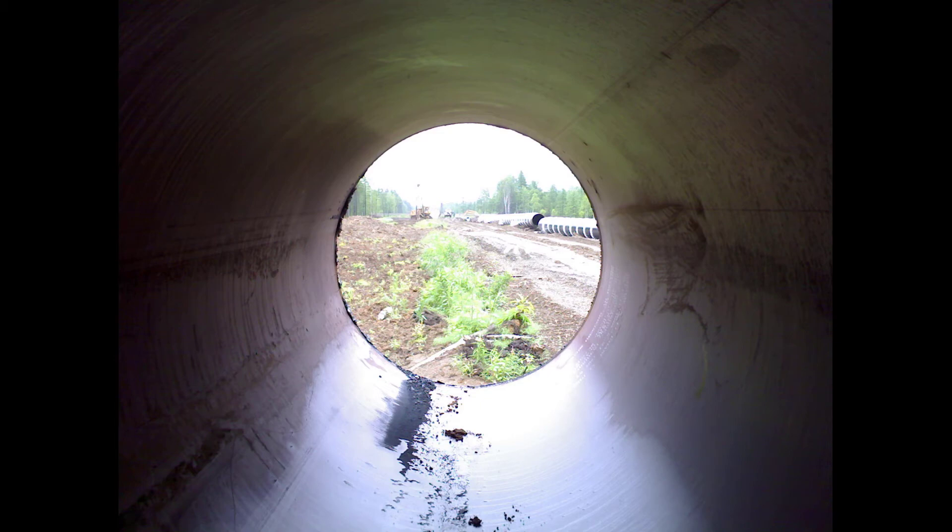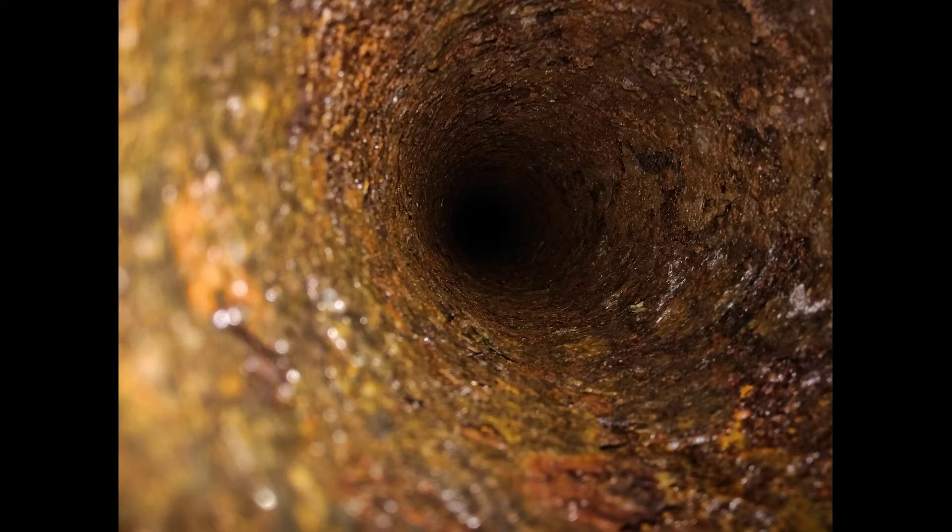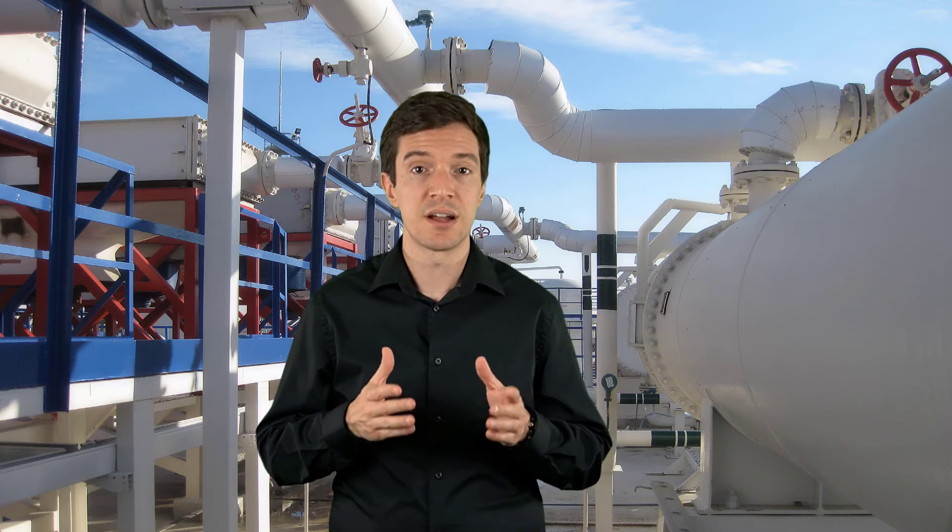For smooth pipes, the Darcy friction factor is a function of the Reynolds number. In real world, however, pipes are not smooth. Each pipe has its own surface texture. For example, a new pipe can be fairly smooth, while an older pipe can be corroded and rusty, so its internal surface is rougher. The surface texture of a pipe can be described as a sand roughness height or through an equivalent grain roughness height.